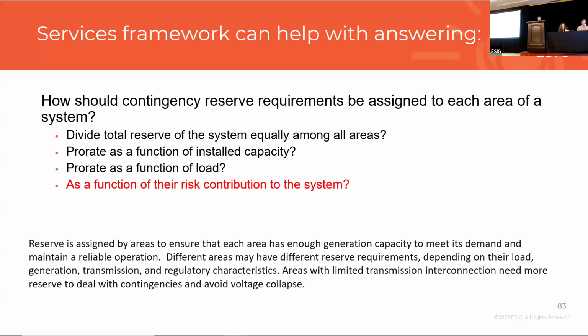But today, reserves are typically allocated so that each area has enough capacity to meet its own demand and any contingencies, so that if islanding occurs, it can be self-sufficient. The question in this context is how to allocate reserves across each area — should it just be divided like the total system reserve? We usually study loss of the largest generation as our frequency response criteria, and that loss of largest generation will occur in just one portion of the system.